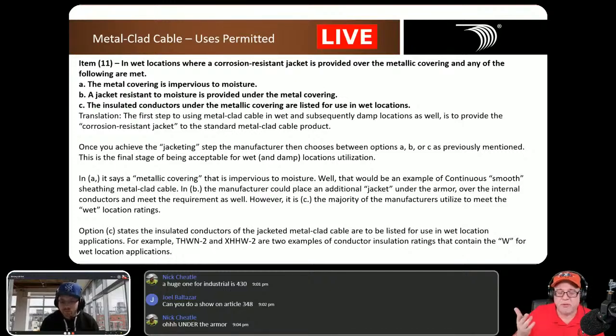Okay, so just to explain it, I could have THHN, for example, inside of that and not THWN, if they made it anymore. It's all dual rated now. But I could have it in there because I have to put that jacket resistant to moisture over top of it first. And then I put the armor over it. And then I have to meet the general rule: I have to put a corrosive resistant jacket over it.